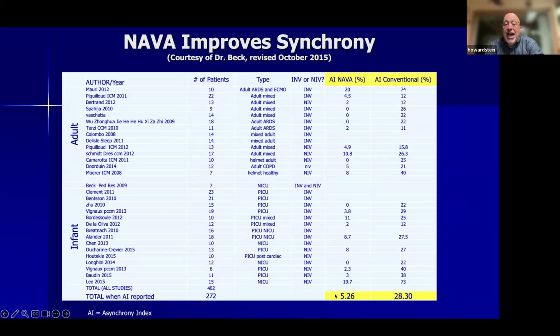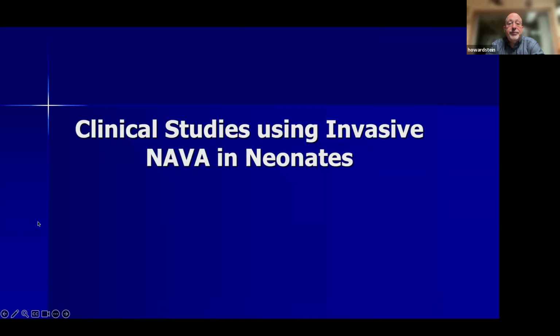So you can see with NAVA here on the bottom, about 5% of the breaths are asynchronous, whereas with conventional ventilation, about 28% of the breaths are asynchronous. Remember, with conventional ventilation, that 28% asynchrony is initiation only, whereas this 5% of asynchrony is initiation, size, and termination. So a much higher bar, and yet much superior synchrony.